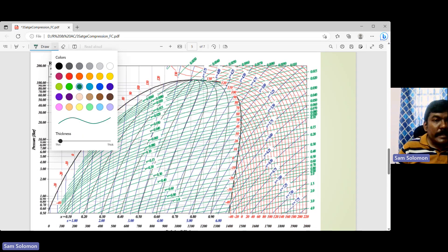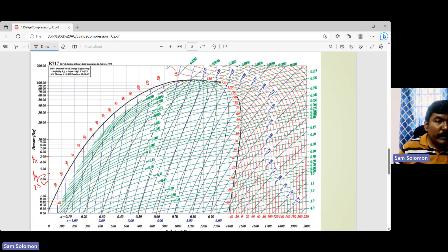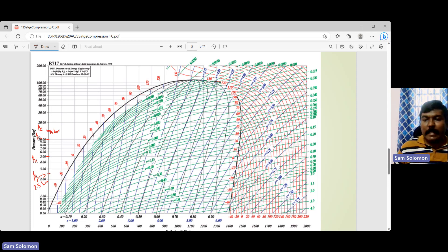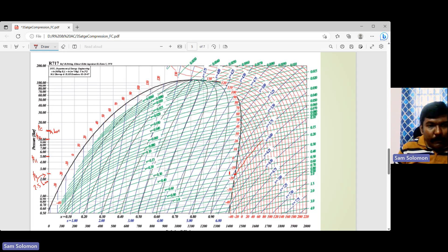On the P-H chart, starting with the evaporator pressure at 2.5 bar, then 5 bar as intermediate pressure 1, 10 bar as intermediate pressure 2, and 15 bar as the condenser pressure. Point 1 is on the saturated vapor line at 2.5 bar. Traveling along the constant entropy line to 15 bar gives point 2.